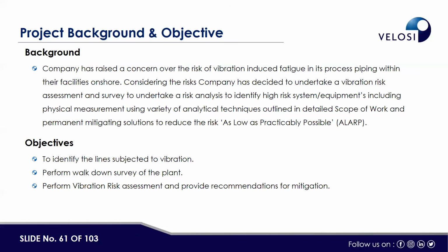Once we observe the vibration above the acceptable level from the Energy Institute, what do we have to do as the next step? The next step is, maybe there could be a design change required, or you may have to add new supports or anchors, or third, you may have to take some corrective action with the help of operation. The level of exceedance also has to be known, whether it's low, medium, or high, and then accordingly the decision has to be taken by the technical department with the help of operation. This is normal practice, sir. Okay. Thank you, sir.